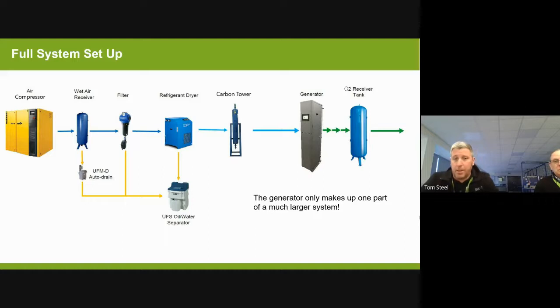Okay, so there's a lot of parts that need to be maintained. And if they're not maintained properly, these will cause issues with either the gas going in or the gas coming out. And it will show up as a purity issue. Sometimes it'll show up as a low pressure fault, but in turn that will essentially come to a purity issue eventually. So if you have a look at the full system setup we have here, we've got air compressors.